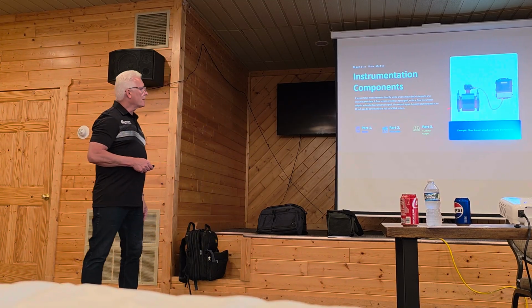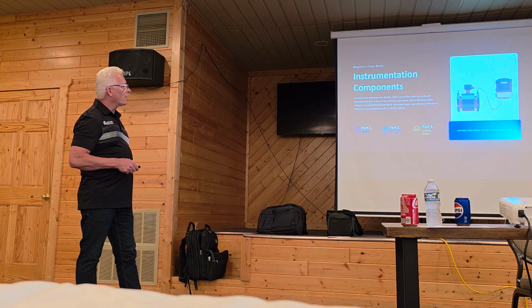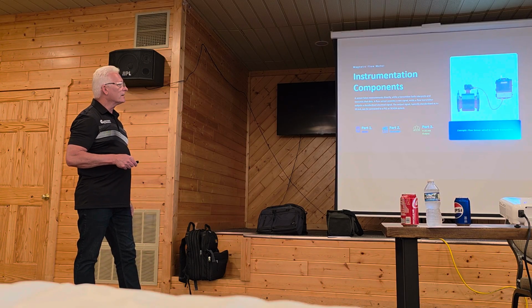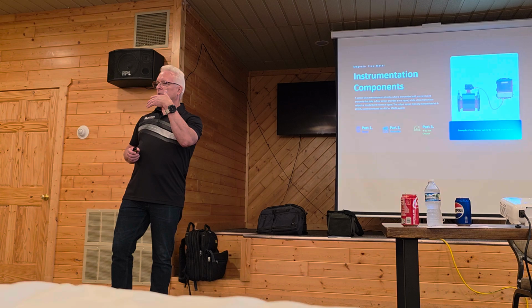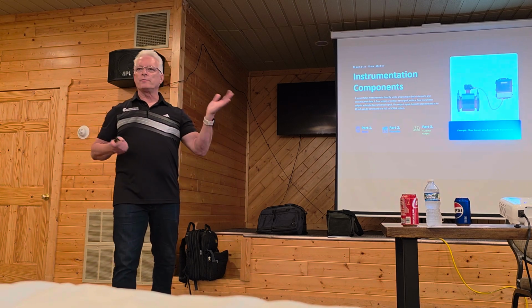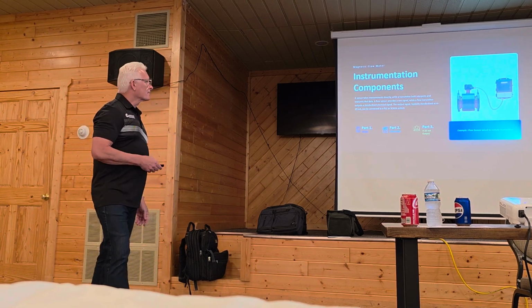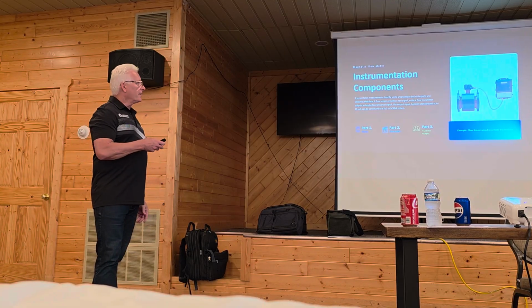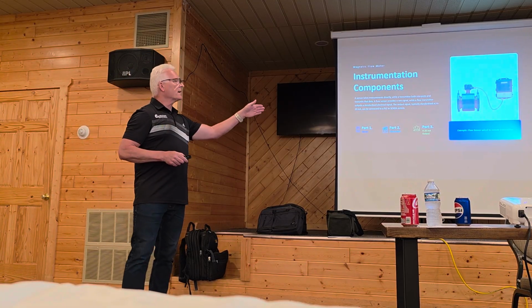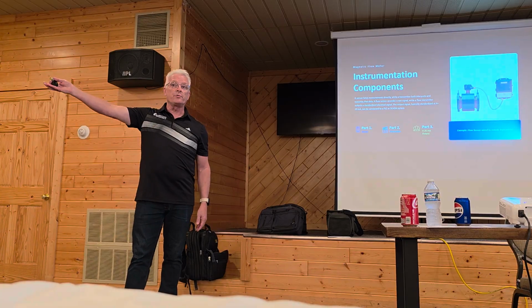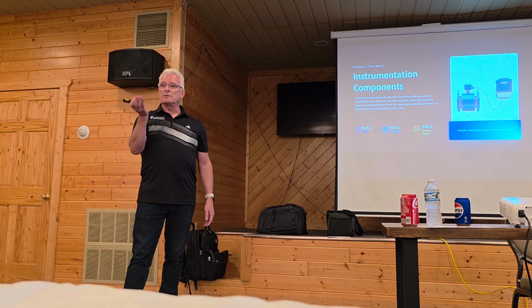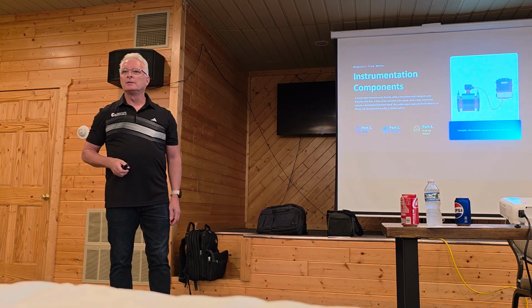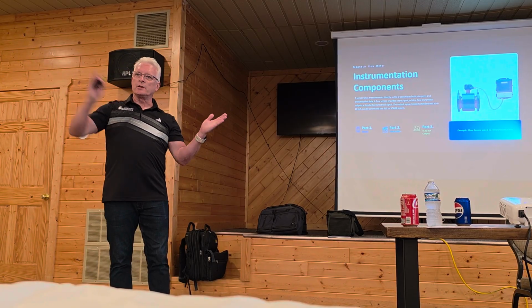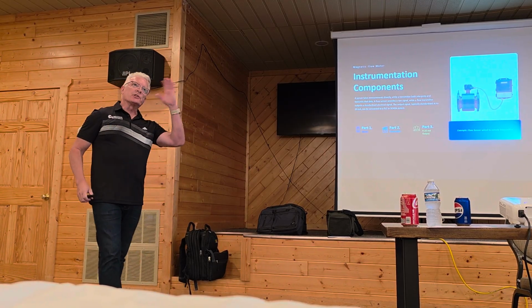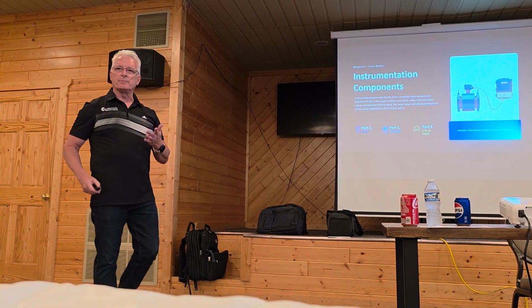We do a full calibration. We not only do the flow part, we also do the 4 to 20 out to make sure it's correct going to the PLC, the chart recorder, or whatever device it's going to. Otherwise, you're only halfway there. For example, if this was 0 to 1,000 gallons per minute, and your PLC was set for 0 to 2,000, when you're at 1,000, it's only going to show half the flow because it was set for twice as much. That's an extreme, but it's a good example.